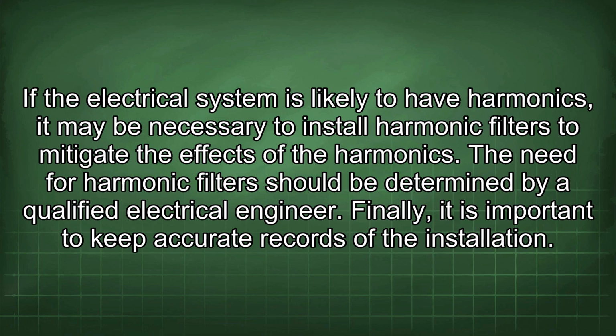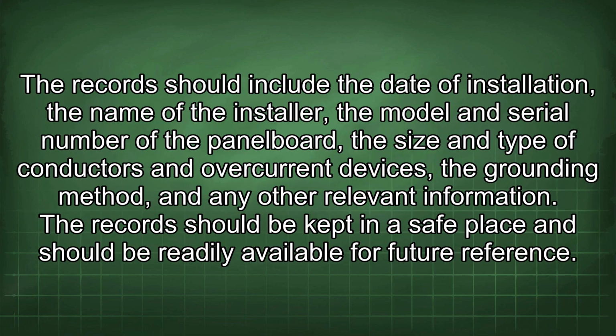Finally, it is important to keep accurate records of the installation. The records should include the date of installation, the name of the installer, the model and serial number of the panel board, the size and type of conductors and overcurrent devices, the grounding method, and any other relevant information. The record should be kept in a safe place and should be readily available for future reference.